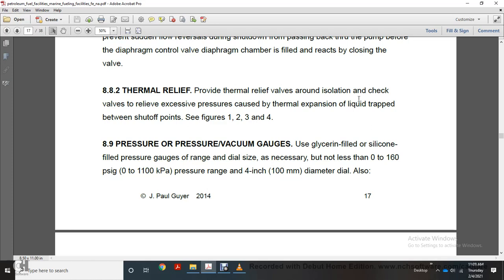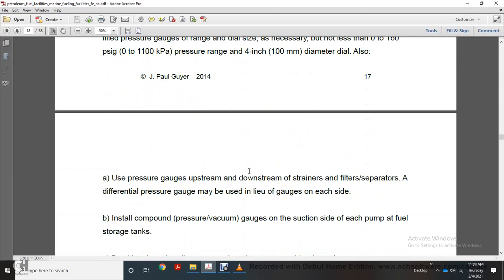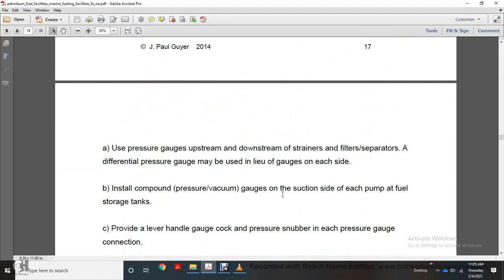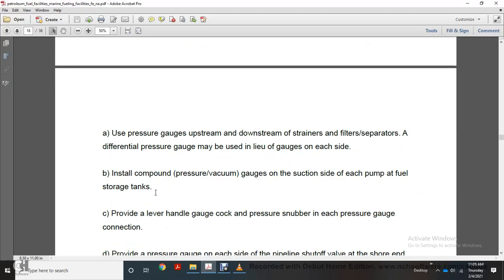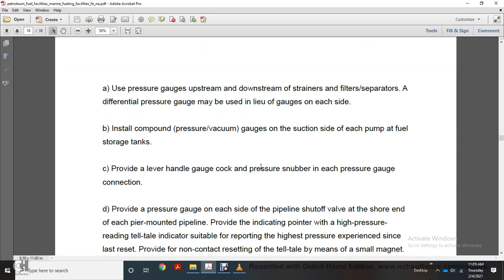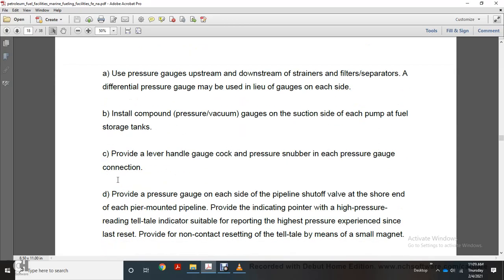Pressure vacuum gauge. Use glycerine or silicone filled pressure gauges with a range dial size of not more or less than 0 to 160 psi gauge pressure range, 4 inches in diameter. Also use pressure gauges upstream and downstream of a filter separator, with a differential pressure gauge. On each side, install compound pressure vacuum gauges on the suction side of each pump from fuel storage. Provide a lever handle gauge cock and pressure snubber on each pressure gauge connection.